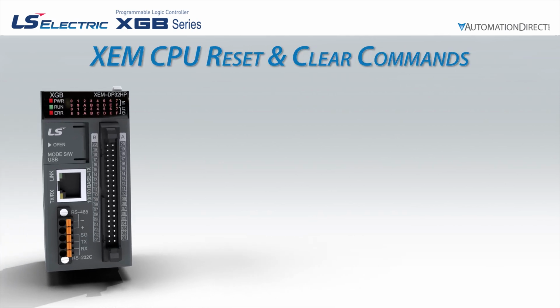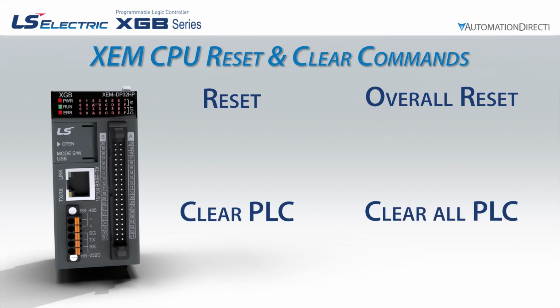The XG5000 software has multiple levels of CPU resets. The programmer has the option to use the reset command, the overall reset command, the clear PLC command, and the clear all PLC command. The reset command performs a simple reboot of the CPU. As the CPU completes the rebooting cycle, it will delete error and warning information to allow the boot up. If an issue remains, the error or warning will come back.